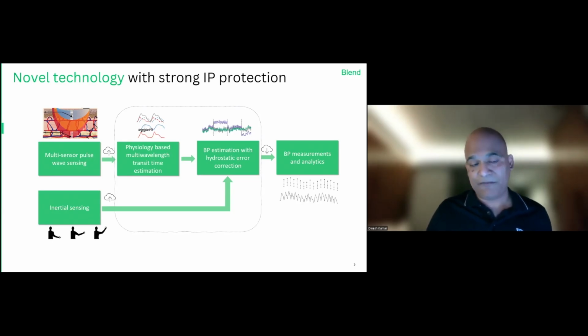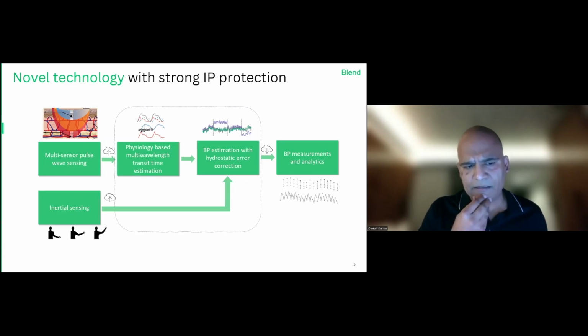And that's really one of the underlying key IP, intellectual capital as well: how we combine that information from brachial, or rather onto brachial, to convert into blood pressure. Additionally, we measure the arm position using our inertial sensors, and based on whether the arm is fully rested and where it is, we can correct for that. It's called hydrostatic error correction, which you can think of as the water column or mercury pressure, the additional pressure from the heart relative to the location. So if it is below the heart, then pressure will be higher. If it is above the heart, pressure will be lower, and we correct for that. And that's actually one of the biggest bottlenecks with wrist-based devices, in addition to the vascular geometry being very prone to noise, reflections, and slight slips.